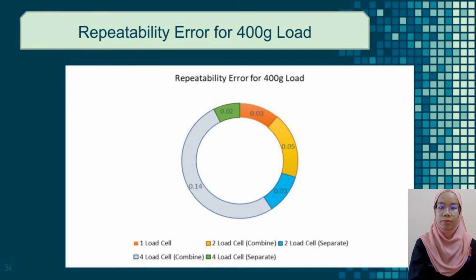Okay, the highest repeatability error, 0.14 gram, was in the test using 4 load cells combined together on one platform. Then the lowest error among all was in the test using 4 load cells mounted separately on each of the 4 platforms.